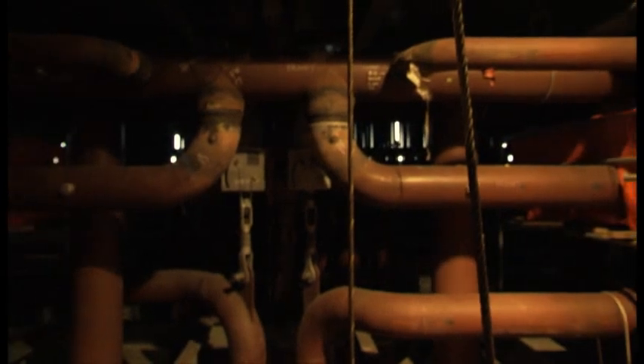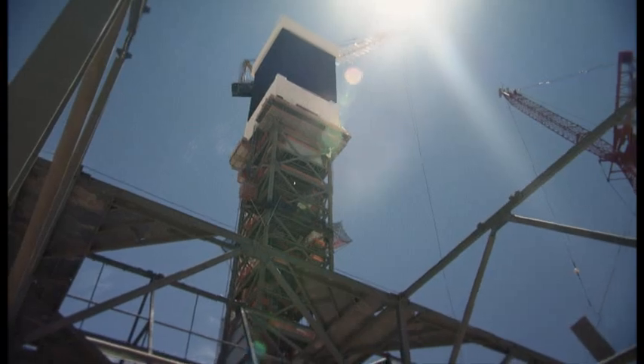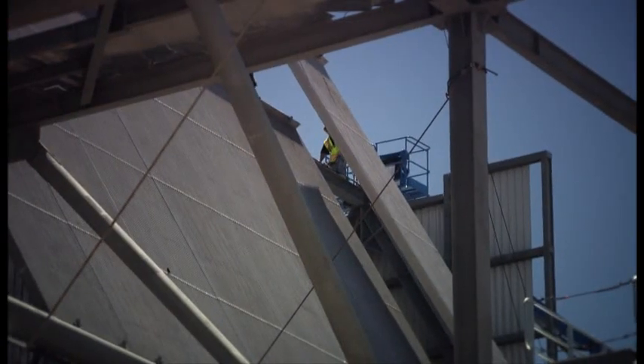There's no room at all. You've got all the penthouse, everything — all your crossover tubing, your headers — everything is inside of the water walls, and it's 44 foot square. So everything has to fit exactly like it's supposed to on the drawing. We have to take the time to make sure everything is prepped properly before it goes up to save any additional rework up on top.